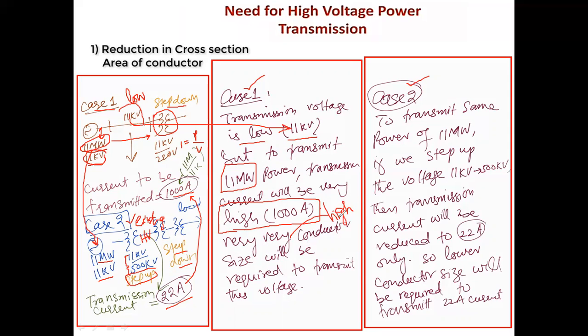So a very, very high conductor size will be required to transmit this huge amount of current. And we will discuss in the upcoming slides that the conductor size increases with the increase of current flowing through that conductor. So for the 1000 ampere current, we need to have a high conductor size.